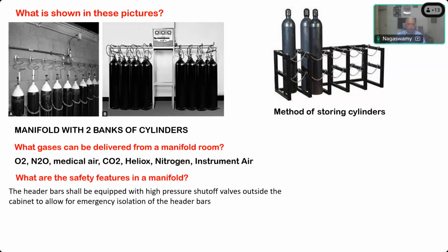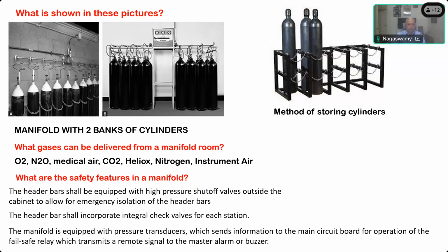If you open that, there will be a lever which you can just use. So the cut-off valve should be outside the cabinet, and the header bar shall incorporate integral check valves for each station, and the manifold is equipped with pressure transducers. It sends information to the main circuit board for operation of the fail-safe relay, which transmits a remote signal to the master alarm or a buzzer.